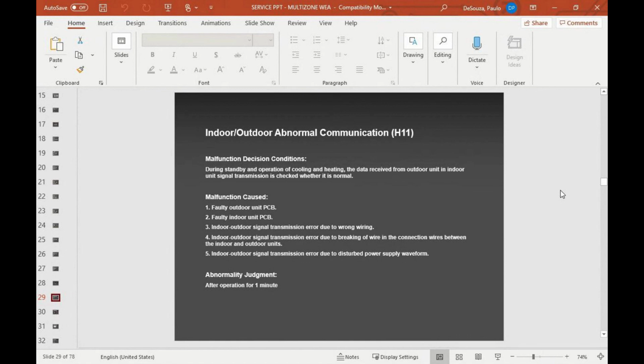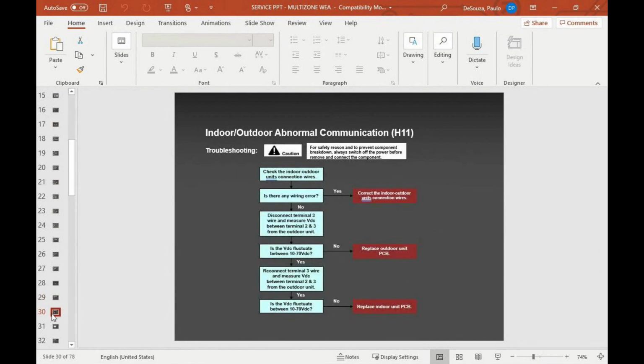H11 is the first error code in my slide here. It's because it's the most common error code. It is so simple to find out where the problem is, whether it's the inside or the outside. So in this slide, it tells you that the indoor PCB is defective or the outdoor PCB is defective. Now that can be a problem on a system that has been running for ages, for years. But that's not a problem. You don't have that problem, indoor-outdoor PCB defective, when it's a brand new install.